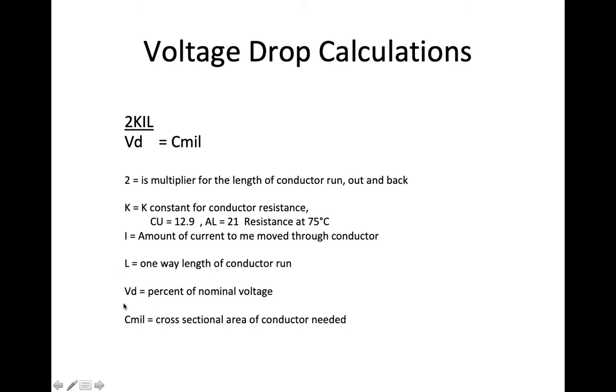Voltage drop on the denominator is the percent of nominal voltage. So if I'm trying to get 3% of, or let's say 5%, the math is a little bit easier. 5% of 120 would be, 10% of 120 would be 12. 5% would be 6. So my denominator would be 6, or 5% of 120 volts. And then the answer will be given to me in cross-sectional, or Cmil, number.